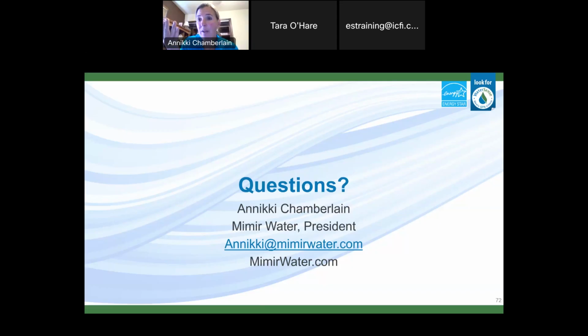Is that water quality consistent? Can you just get a treatment program, or is it changing all the time? But really, it's no different than any other incoming water quality. Just have to see what the quality is. I assume if it's reuse, it's going to be a little bit higher in concentration in minerals before it comes in. Honestly, the probably biggest savings is just operating at optimal, or there's these things called adiabatic condensers.